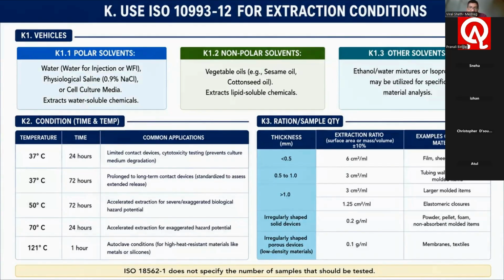So the standard says to follow the specific ratio, and your samples must be available for the extraction that is being used for the testing. It depends on the quantity, that is, surface area or weight in grams of your devices. So you should follow the ratio given in the table, depending on the nature of your devices, and ensure the minimum quantity of your device is used. Firstly, you should identify the minimum quantity required for the test. Then you should identify which temperature conditions are used for the extractions. They have given different parameters for extraction temperature and time. So your device is submerged in different polar, non-polar and other solvents, for a specific quantity, at a particular temperature and time, depending on the clinical use of your devices.